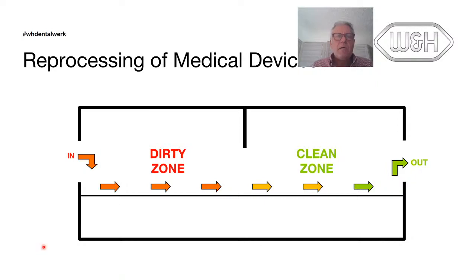This is a virtual reprocessing area. As I mentioned before, this is the virtual dirty area and the clean area. This is just to show you that ideal would be to travel from left to right, in and out. I know it's not always possible, it's always too tight, too small, and we do this in the same area. It's a pity because in this area, as you are brushing, cleaning, transporting instruments, the environmental contamination is much higher than in this area. Usually the airflow for ventilation or air conditioning should flow from the clean area to the dirty area, the opposite way.